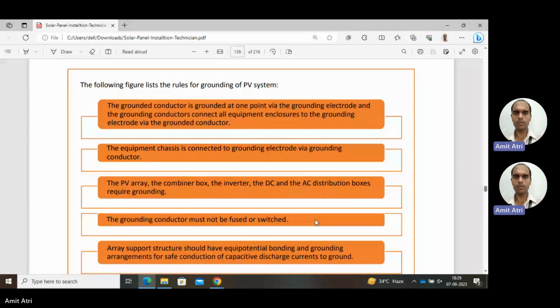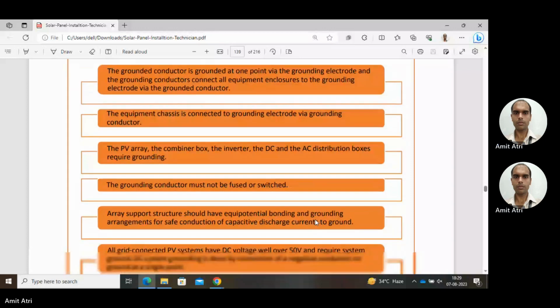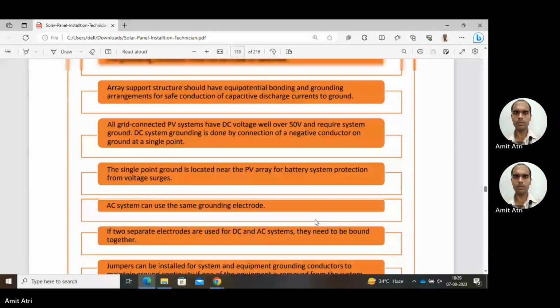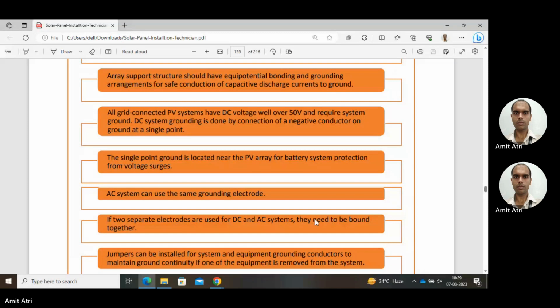The next rule: the array support structure should have equipotential bonding and a grounding arrangement to the supporting structure. That also should be properly connected with the grounding structure. So the capacitive discharge, or we can say the over voltage induced, should also be diverted to the ground in the array support structure as well. So the main components and the supporting structure, all of them have to be properly grounded.